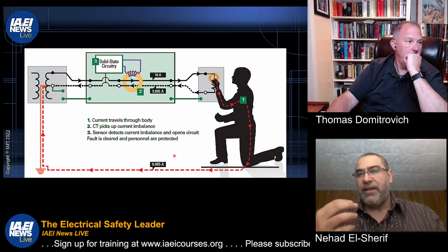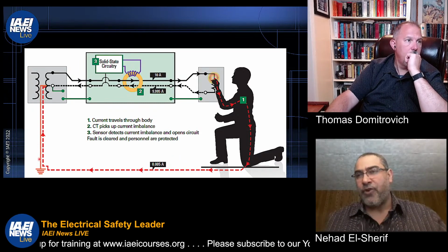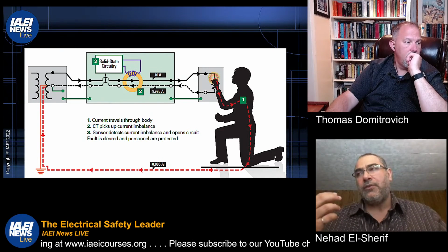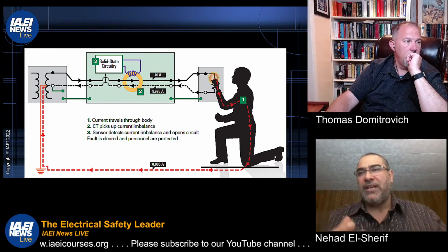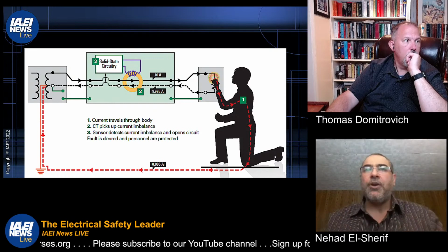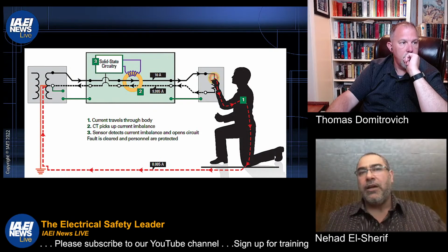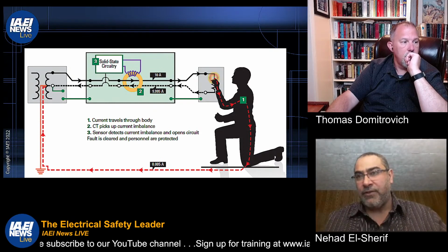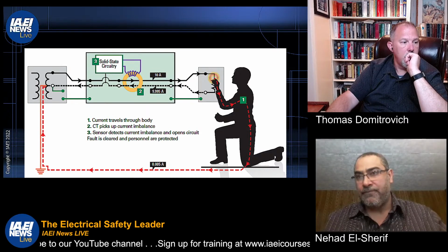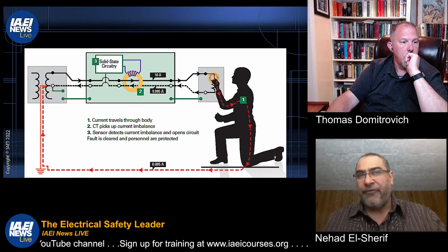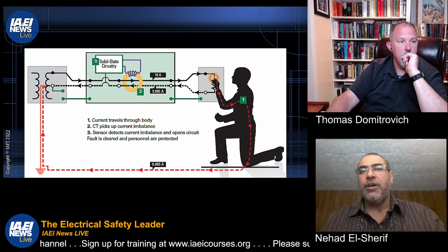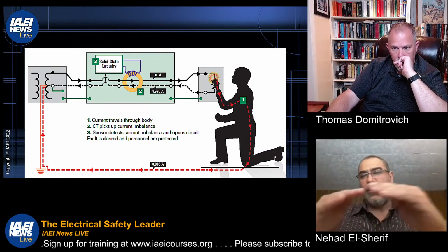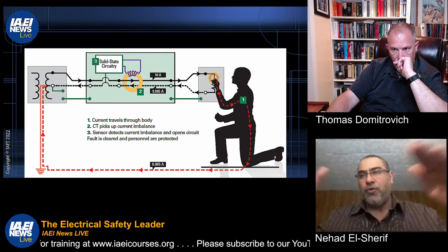So at the end of the day, it's a ground fault that we're trying to protect from. But because the tolerance of humans is much less than machines, like if you have a motor or a pump or any piece of equipment, equipment can tolerate much higher values of ground fault going through them without starting a fire, without having a failure or problem, right? So we have to split the idea of ground fault protection into two categories.